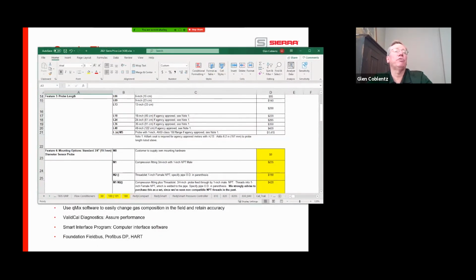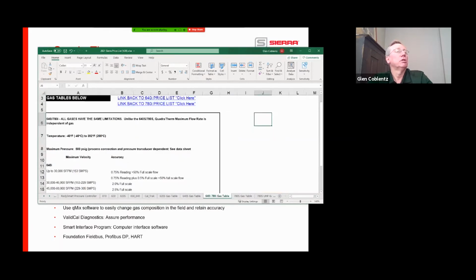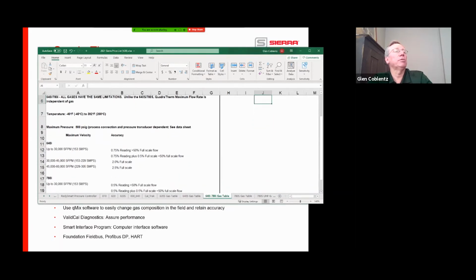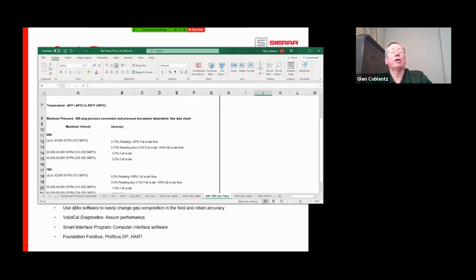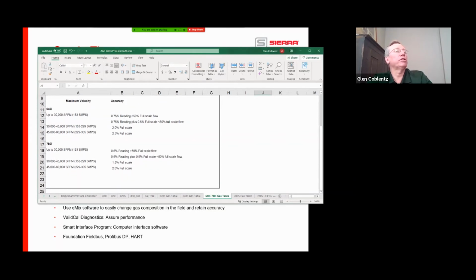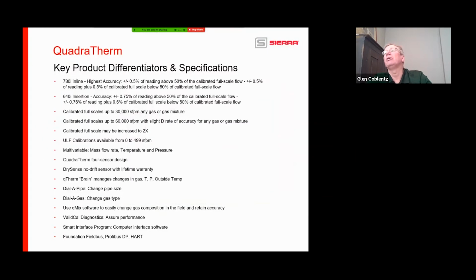Here is some powerful information: all these different gas tables. There you can see the accuracy statements for both products, of what the standard feet per minute is. Remember, standard feet per minute times the area of the pipe gives you standard cubic feet per minute. We'll have a little something later to work on that. So, calibrated full scales up to 60,000 standard feet per minute with a slight derate of accuracy, and that was on that price list.